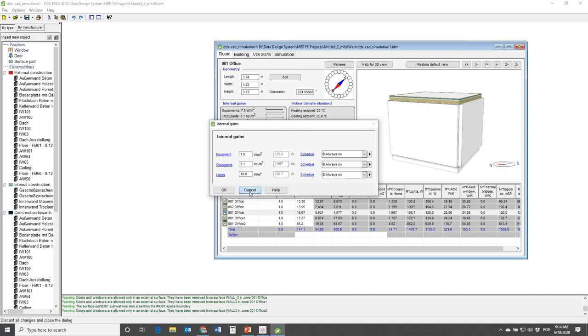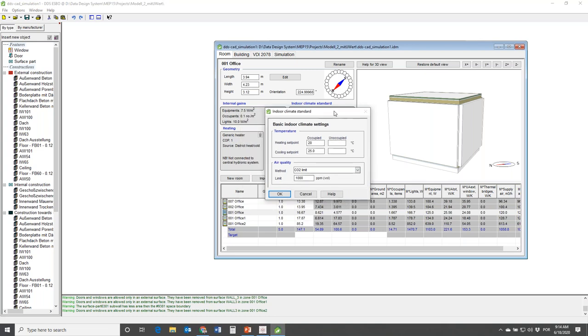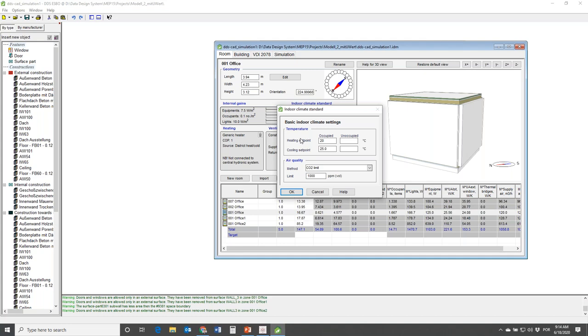Next to Internal Gains is the Indoor Climate Standards. Double-clicking, you can see temperature set points for heating and cooling. We also have a standard for air quality - for CO2 levels. Because the calculations are based on the original IDA system, we have a very sophisticated occupant model that calculates not only the heat emitted but also the moisture, humidity, and CO2 emitted by the occupants. Here you set the maximum CO2 level allowed in the room.